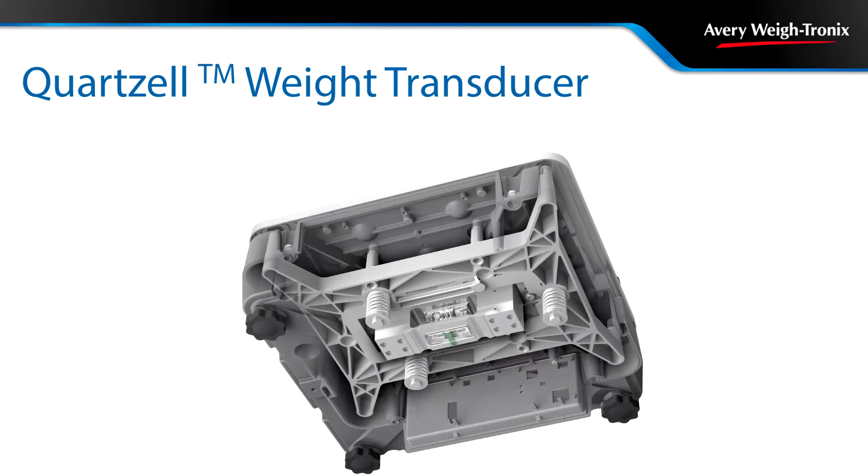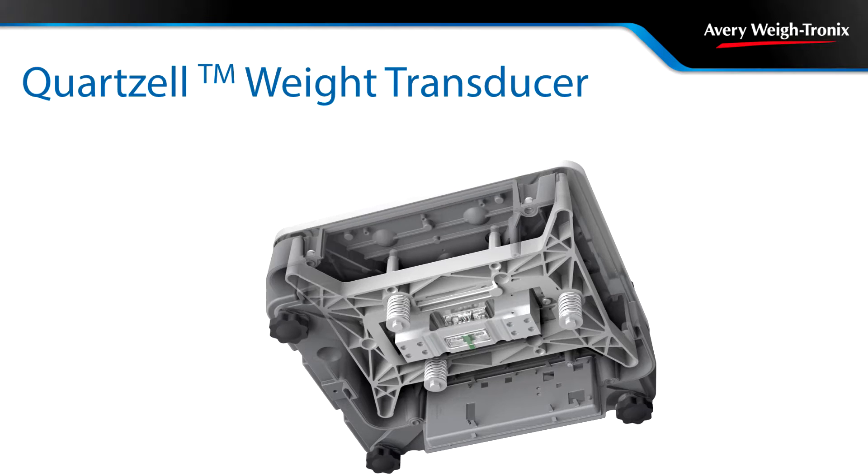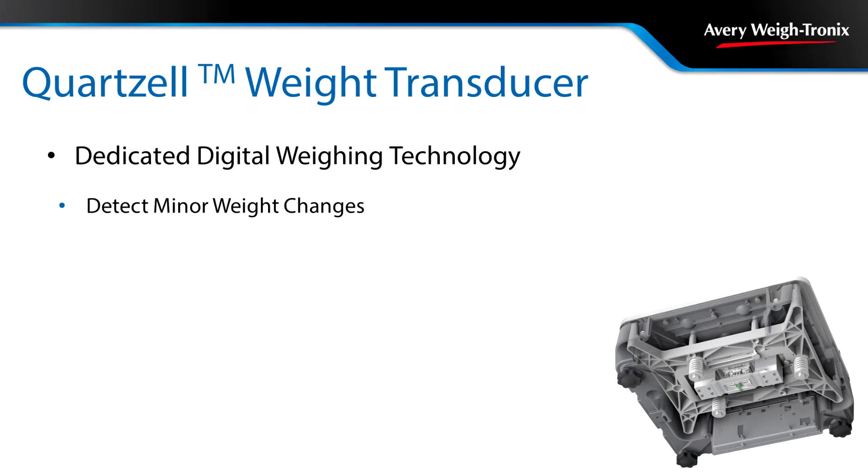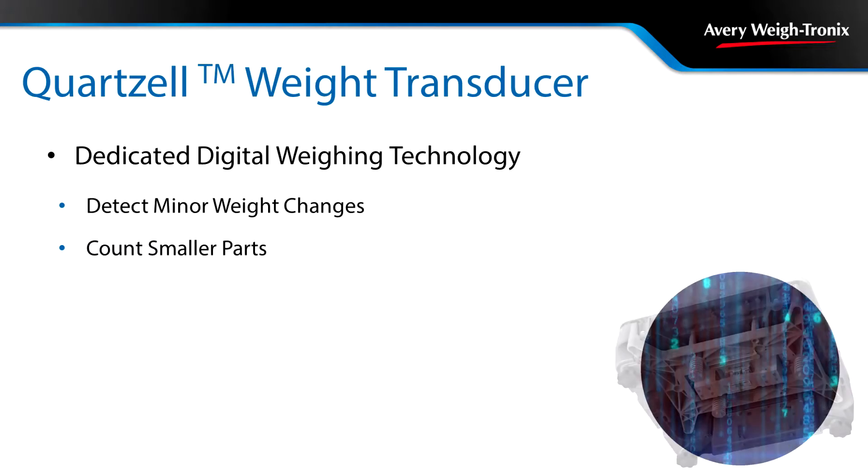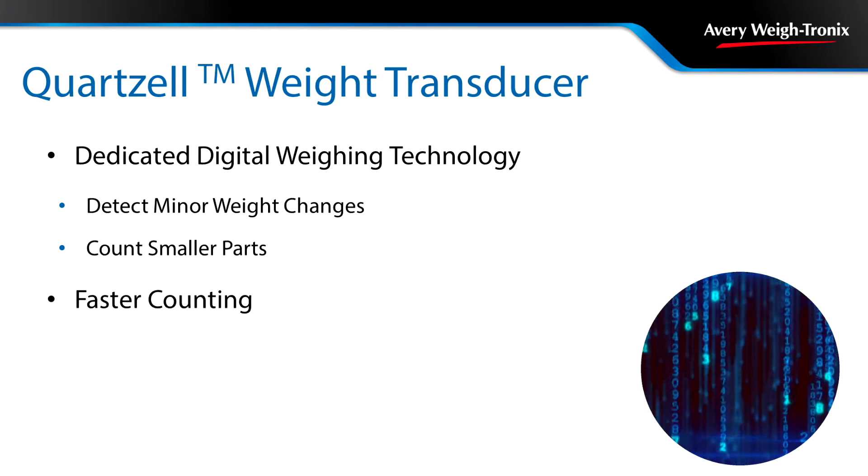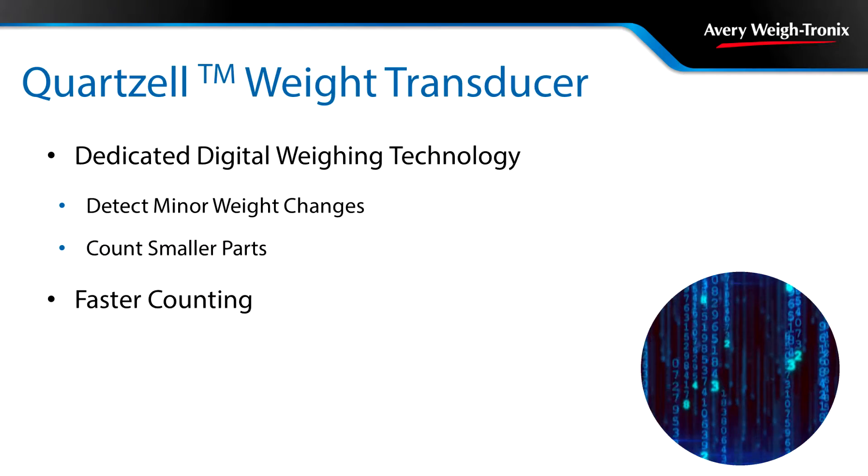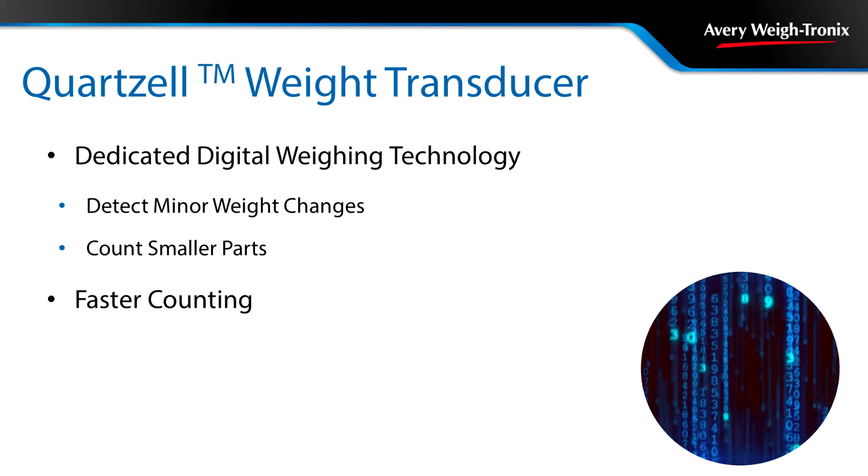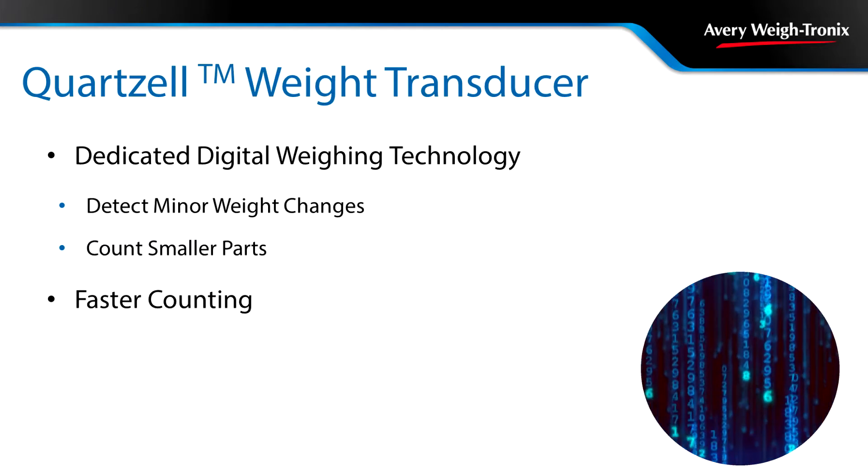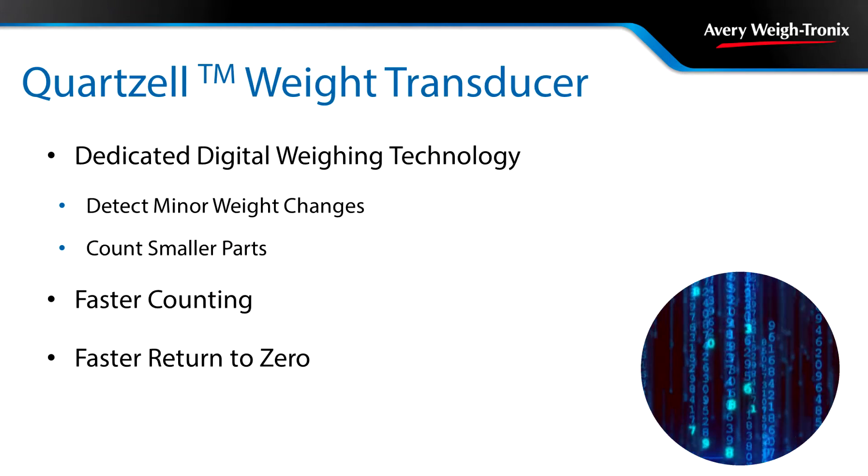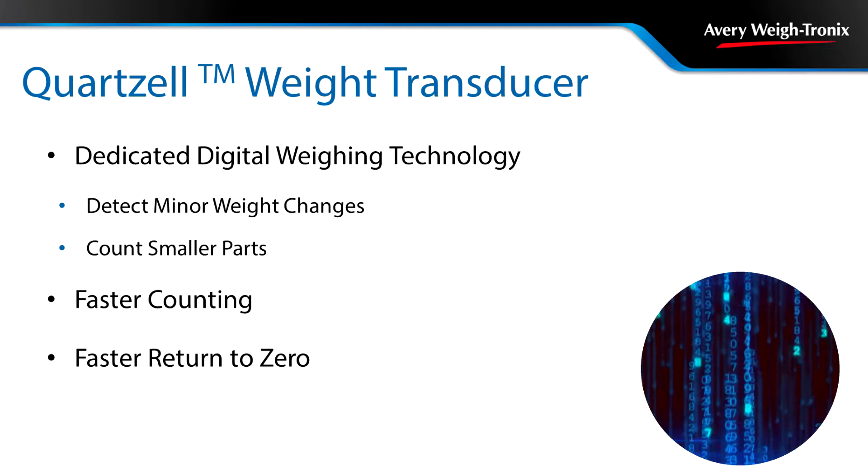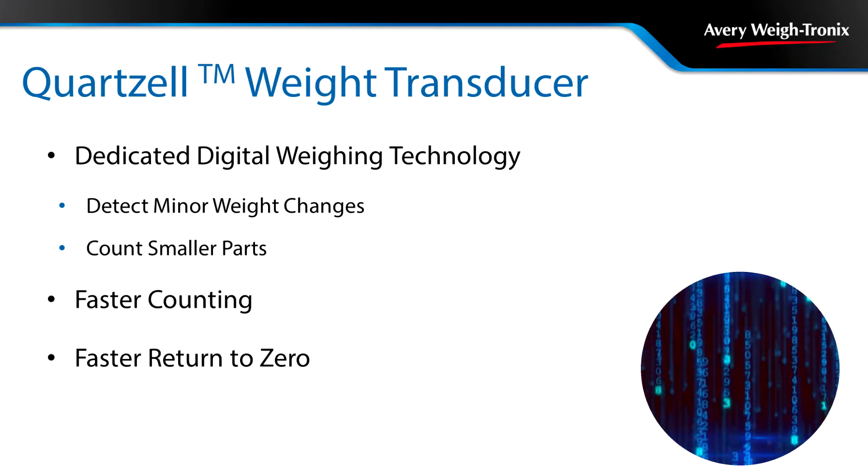The Quartzell Weight Transducer was specifically designed for counting applications. This dedicated digital weighing technology allows the ZK830 to detect even the slightest of weight changes and count pieces as small as 10 mg. Because the signal is digital, the ZK830 weighs faster and with greater resolution and faster return to zero than traditional load sensors.